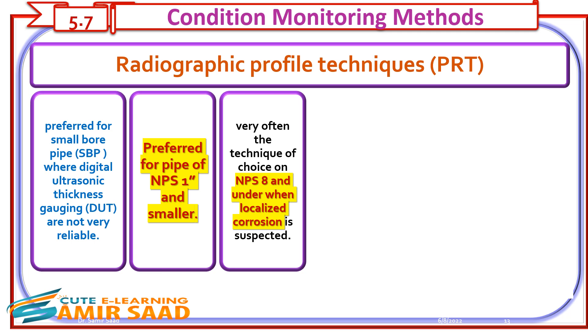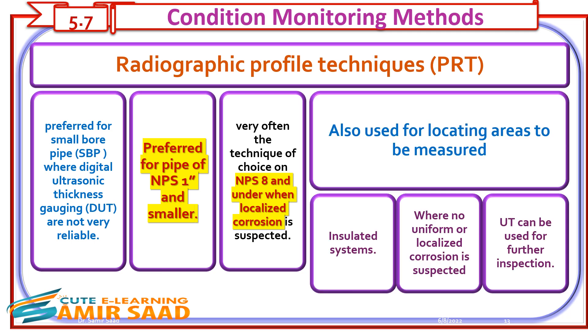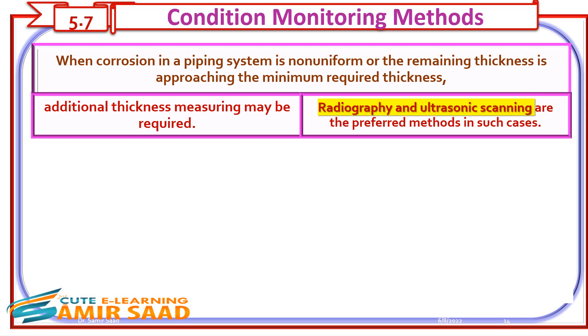Radiographic profile techniques (PRT) are preferred for small bore pipe where digital ultrasonic thickness gauging is not very reliable. PRT is preferred for pipe of NPS 1 inch and smaller, and is very often the technique of choice on NPS 8 and under when localized corrosion is suspected. It is also used for locating areas to be measured in insulated systems where non-uniform or localized corrosion is suspected; UT can then be used for further inspection.